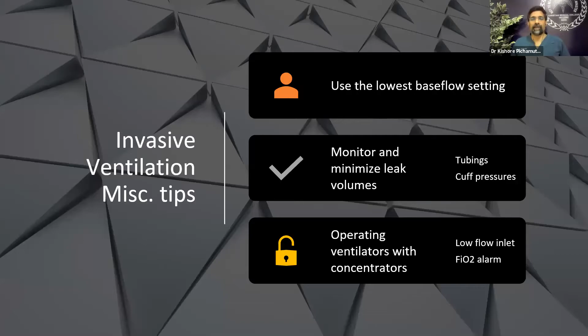The other question that is sometimes asked is, can we connect these small standalone oxygen concentrators to a ventilator? In most cases, no. There are very few models available with what is called a low flow inlet option. The Hamilton C1, for example, is one such ventilator. I know some small rural hospitals which are using an oxygen concentrator and supplying the oxygen into the low flow inlet of the C1 ventilators, and they're managing. So that is something to consider for your next ventilator purchase as well.